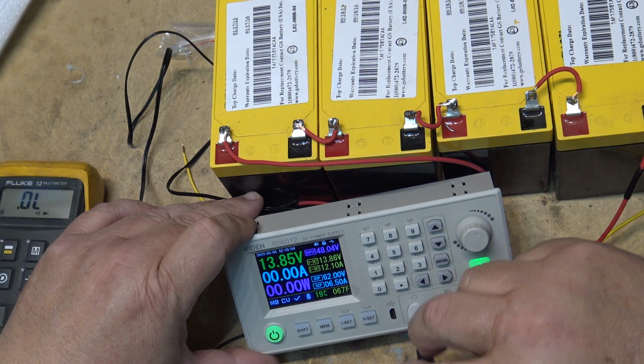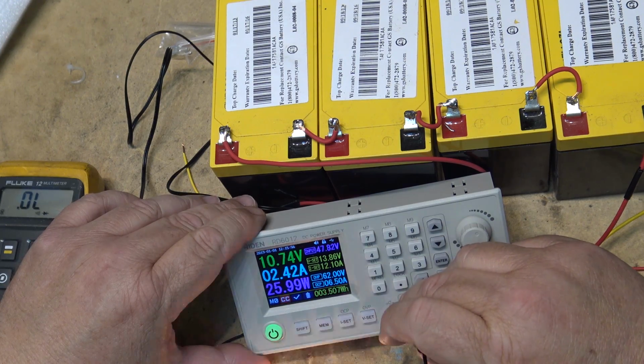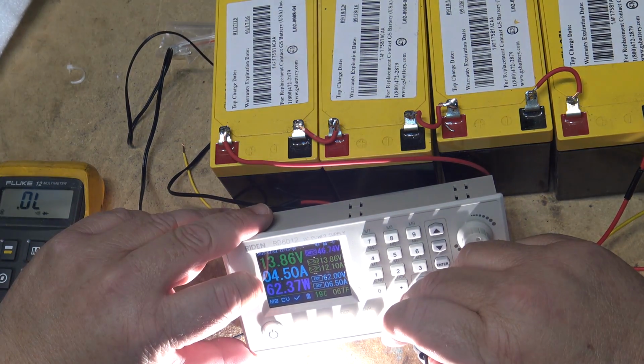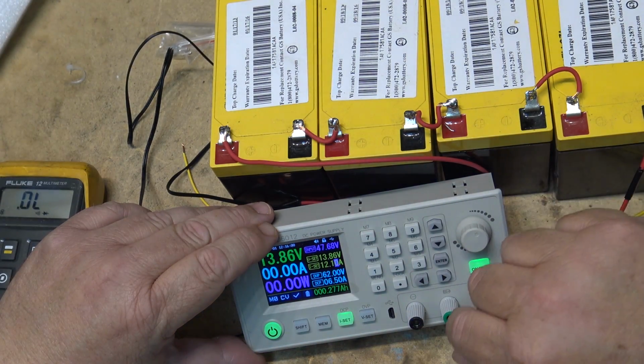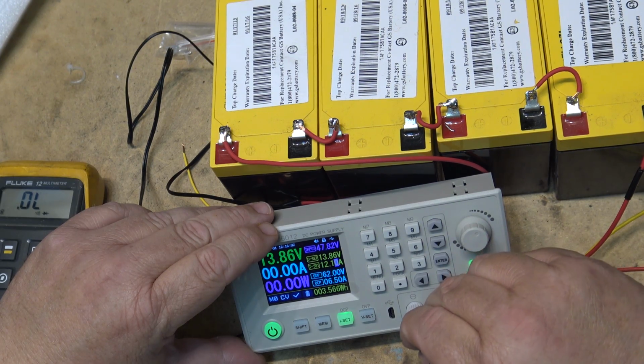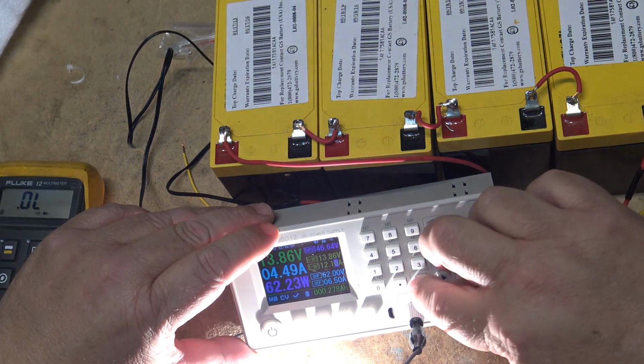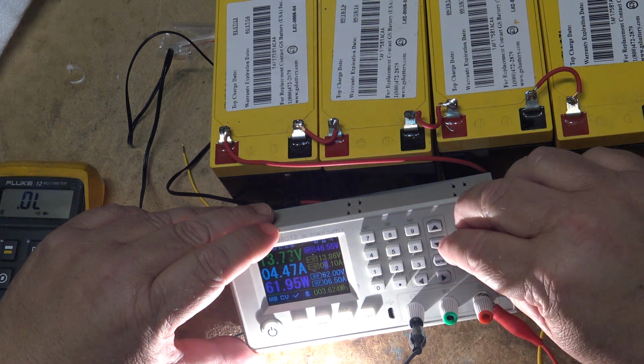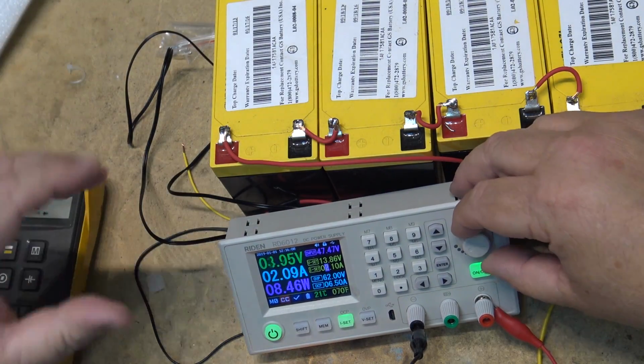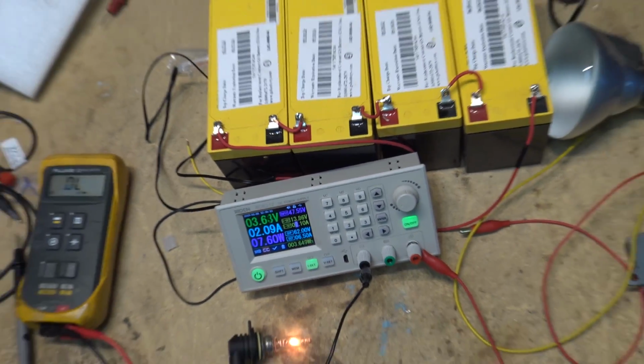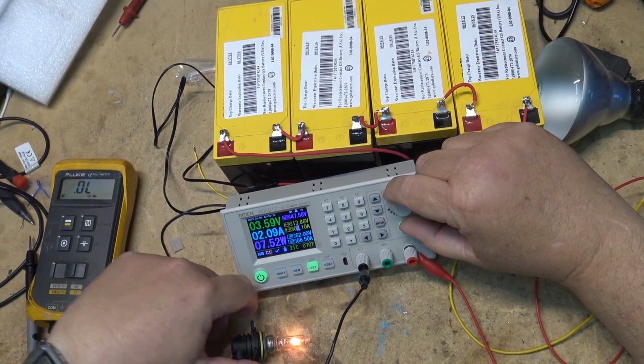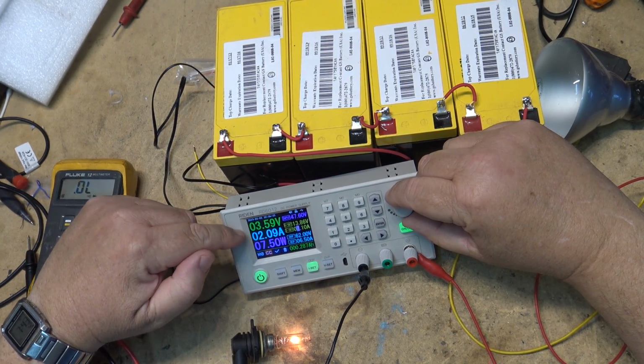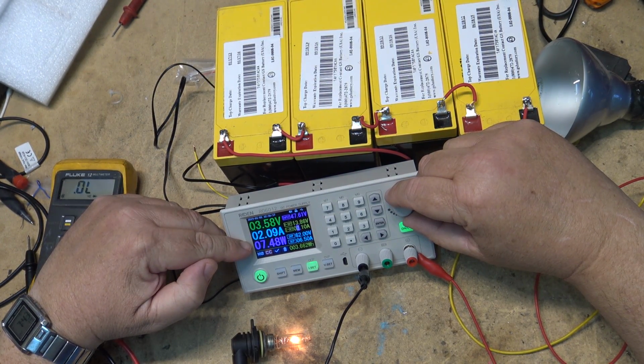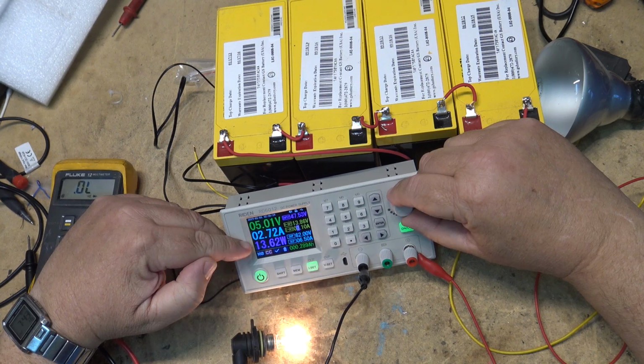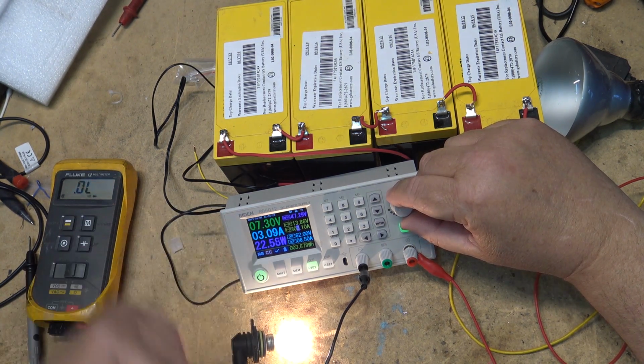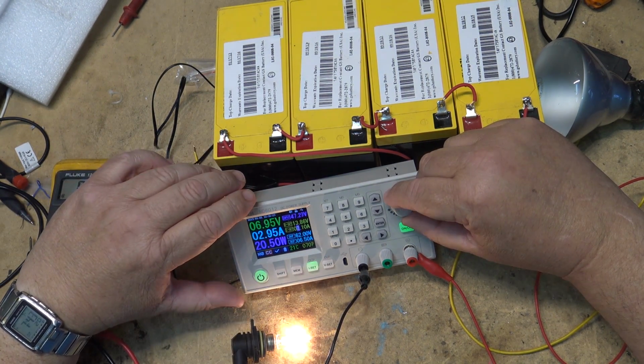Overcurrent protection is now set to 6 amps. Our light lights up because it's only going to draw 4 amps. Now I can take the amperage here and drop the amperage down. As you can see, now I'm limiting. This is the difference between the overcurrent protection and the current limiting. When I'm limiting the current, the voltage is going to drop because I'm limited to 2.1 amps. Right? The unit is not going to shut down with current limiting. It's just going to limit the amount of current.